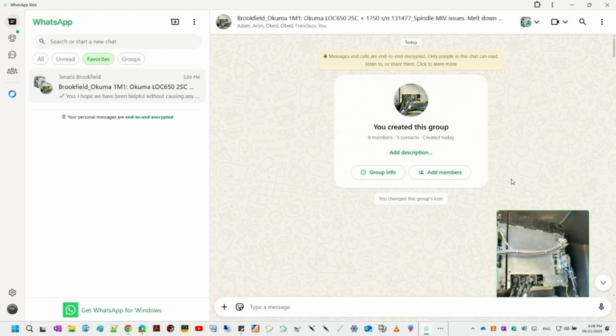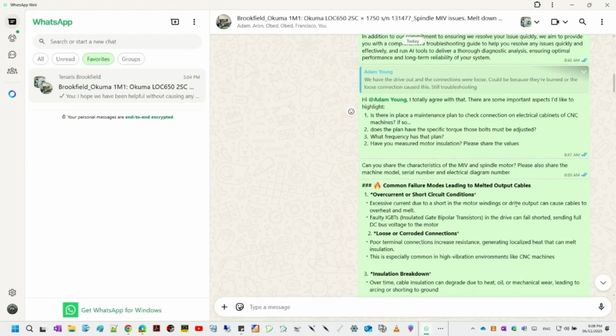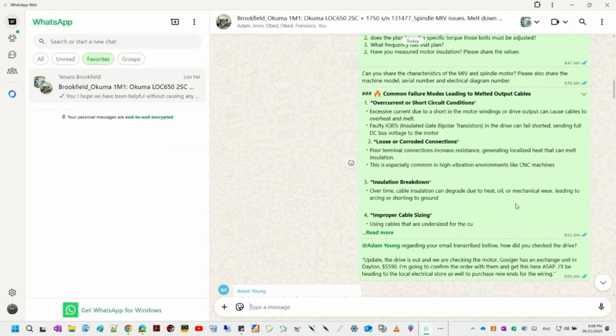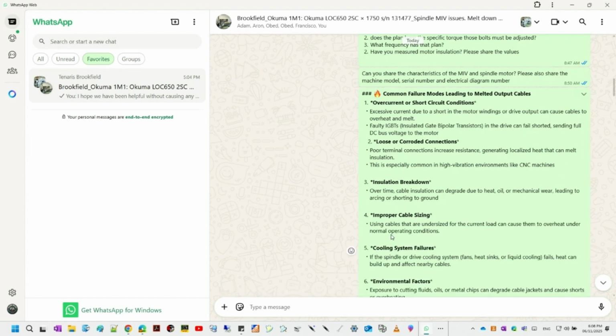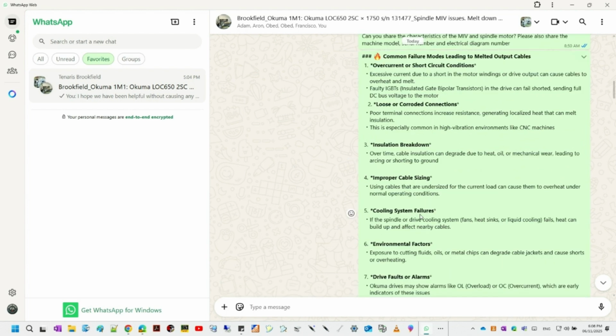Like what? Well, one is pretty straightforward: overcurrent or short circuit conditions, just way too much current flowing, maybe from a fault in the motor windings or a problem inside the drive's output stage itself. Faulty components like IGBTs, those are the big power transistors inside the drive, can fail shorted, which basically creates a direct short circuit. So pure electrical overload from a fault somewhere in the system. Got it. What's another frequent cause?